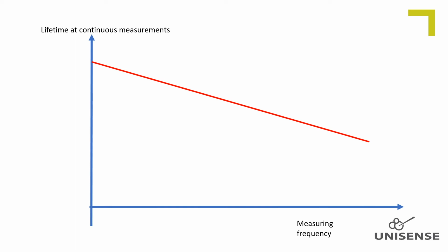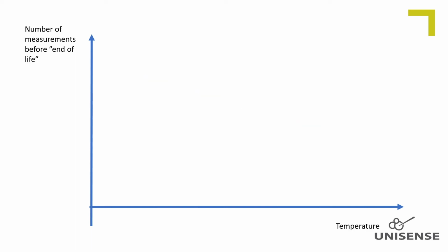In the Unisense software that comes with the optode meter, it is possible to set the measuring frequency to balance the need of data resolution in time with lifetime considerations. Bleaching is faster at high temperatures, and therefore the possible number of measurements before the dye is too bleached to get reliable data significantly decreases at high temperature measurements. Therefore, the optode lifetime also depends on the temperature during measurements. You can check the number of guaranteed points on our website for the different models, which is given for room temperature.